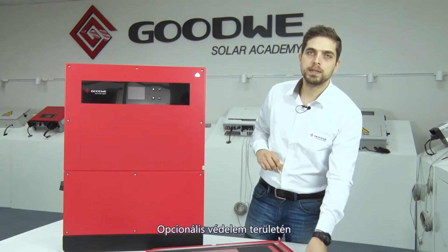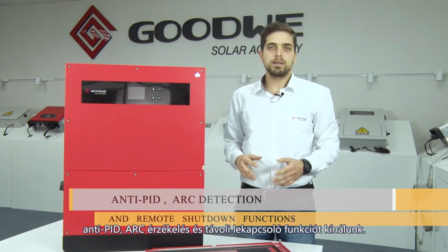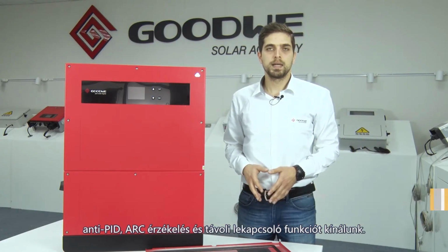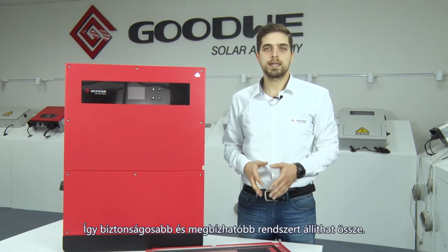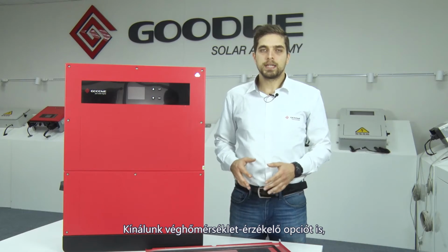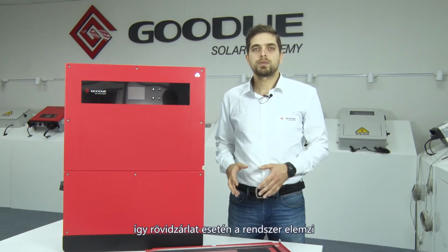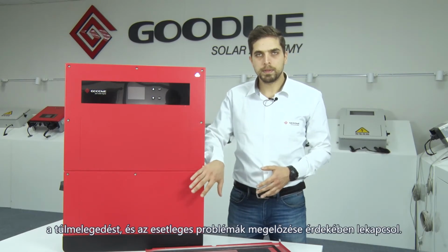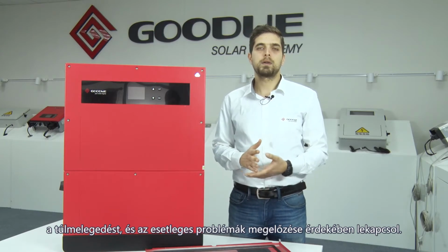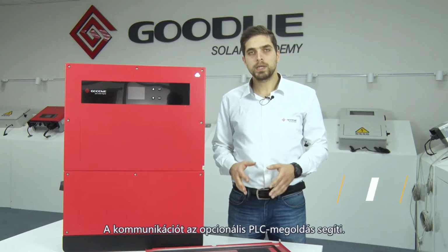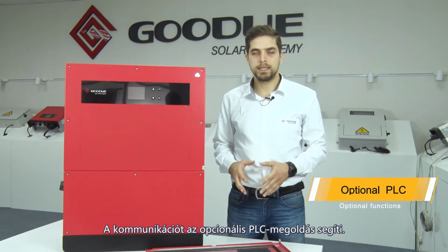For optional protections, we have anti-PID, arc detection and remote shutdown functions. These functions will help you to set up a safer and more reliable system. There is also a thermal temperature detection option. With this one, in case of a short circuit, the system will analyze the over temperature and shut itself down to prevent possible problems. For communication, we have optional PLC solution.